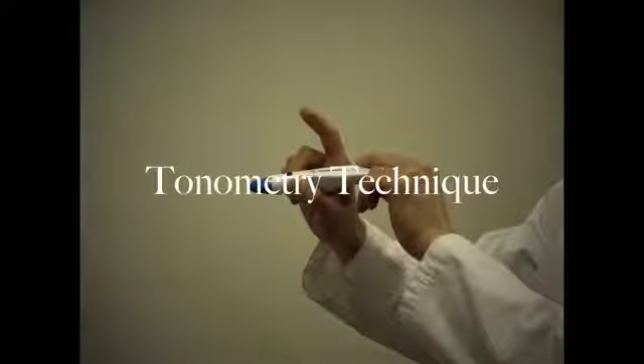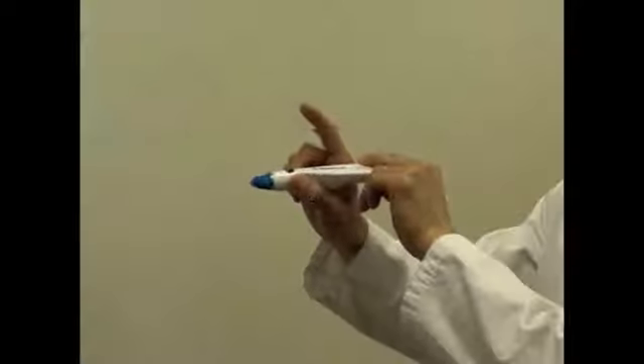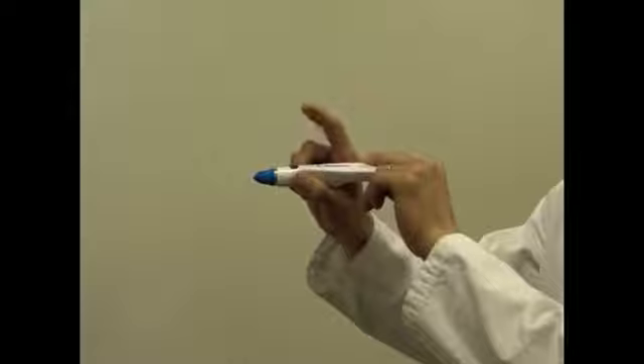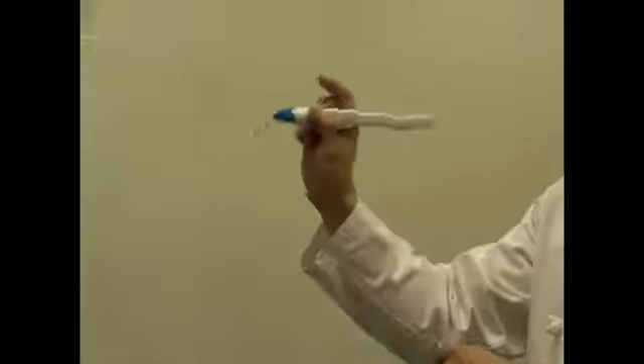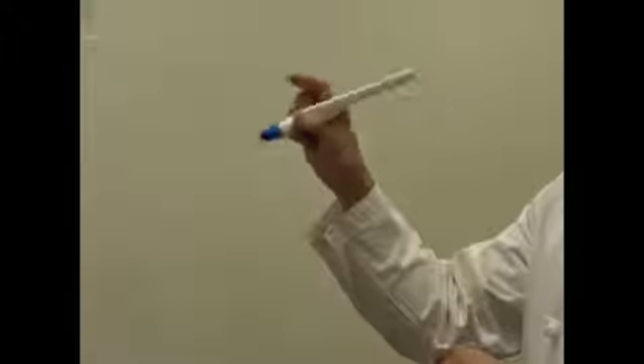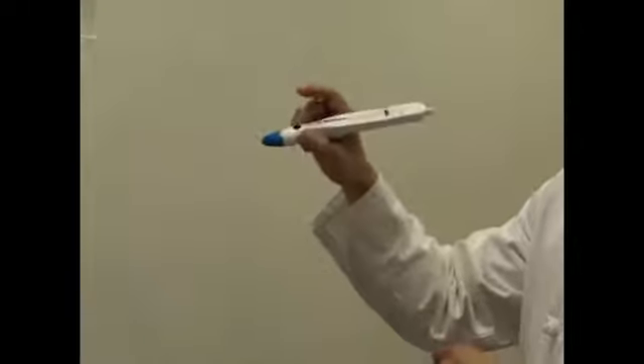Hold the tonometer between your thumb and your middle finger, leaving your index finger available to press the button. Push the black button to activate the tonometer. A double dashed line indicates that the device is ready to take measurements. Do not jab the patient's eye with a tonometer using your elbow. That's too much force. Instead, you will want to use your wrist to take measurements, using a gentle flicking motion.